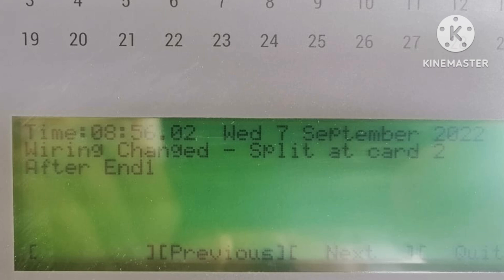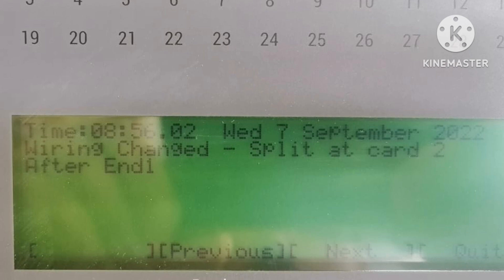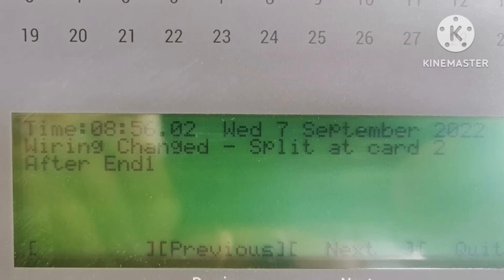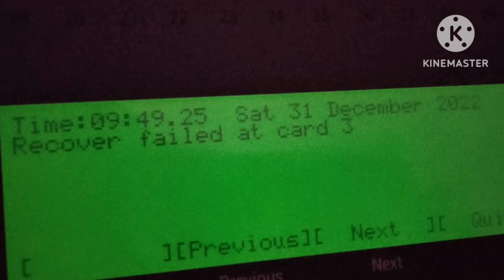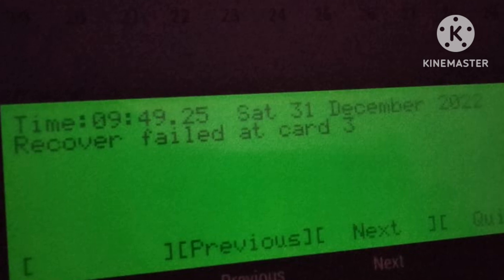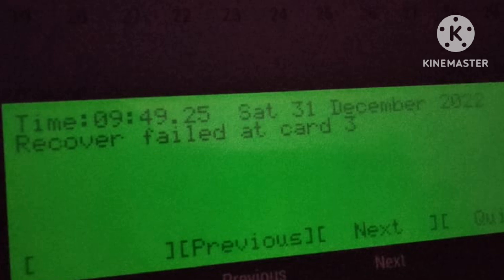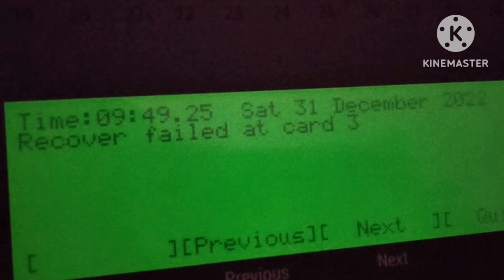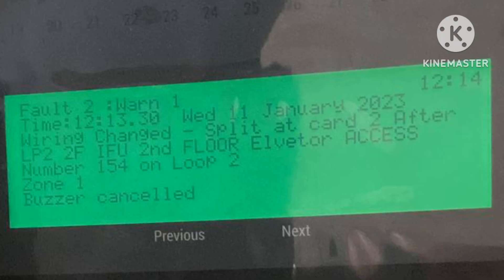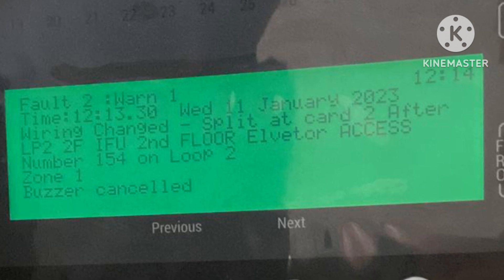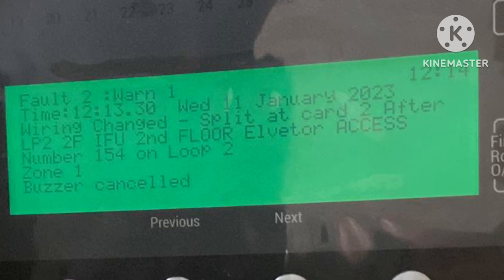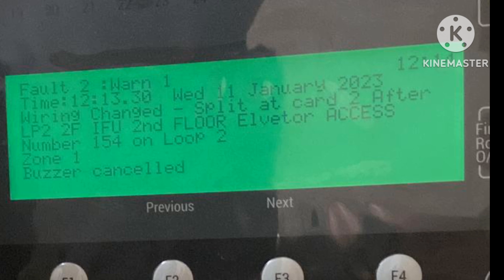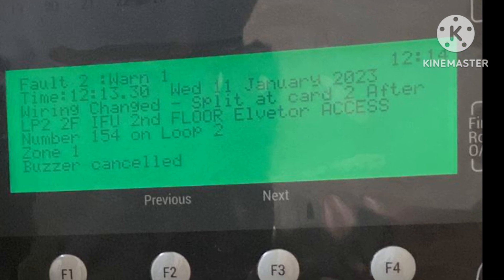Your loop will not restart. First, we have to traverse through the short. The short may be in the loop card, or in the loop field wiring, or at the devices. When you do a relocation, sometimes it stops at the start — meaning there is a short. Sometimes it stops at a particular device, like device number 10. You have to check that device and the ones before or after it, then rectify the short.